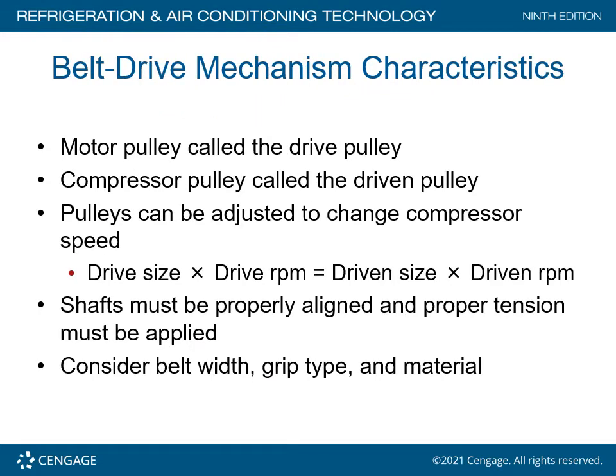Belt driven mechanism characteristics: the motor pulley is called the drive pulley, and the compressor pulley is called the driven pulley. Pulleys can be adjusted to change compressor speed. The formula is: drive size times drive RPM equals driven size times driven RPM. Shafts must be properly aligned and proper belt tension must be applied. Consider belt width, grip type, and material — this is an exact science. If you are changing out belts, you cannot just slip anything on a compressor; it has to be the right type.